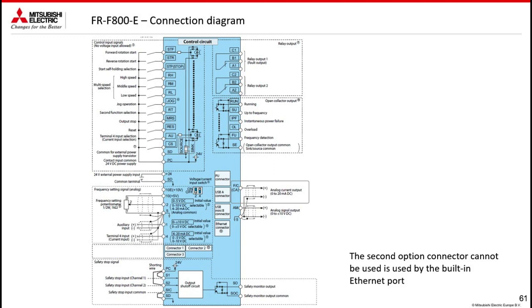AU is to enable analog input 4. So if AU is off, I read analog input 2, while if it is on, I read analog input 4. On the previous model, it would have been necessary to sacrifice an input to parameterize it as AU, so once enabled, analog input 4 is read. CS is the signal to activate flying start. As previously mentioned, there is the possibility of powering the control board through 24 volt on terminal 24.